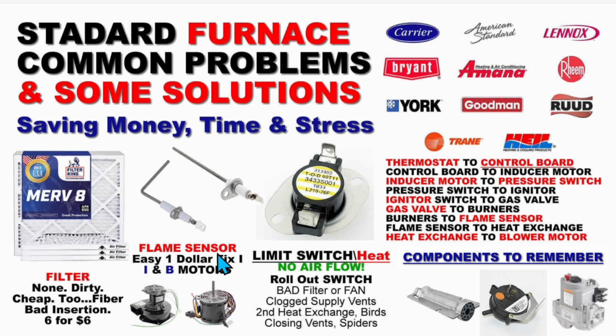In terms of what can fail or what has to be maintained, the inducer motors, they die, but if you keep your filters clean, it's going to really help the longevity of your inducer motor. Blower motors, they die too. That's another thing you want to keep an eye on. Airflow is a big deal. And when you first start the furnace, your rollout switch, that's a safety switch, is going to, of course, do its safety checks. But limit switches are always checking for heat and different things. This switch right here is triggered a lot if you have a dirty filter, if you don't clean your second heat exchanger. There are fans that go out. There are small fans that are around your motors. You want to keep those clean and make sure they operate. If you do trip these things, sometimes you can just kind of tap it to get it to work again. Otherwise, you can just replace these.